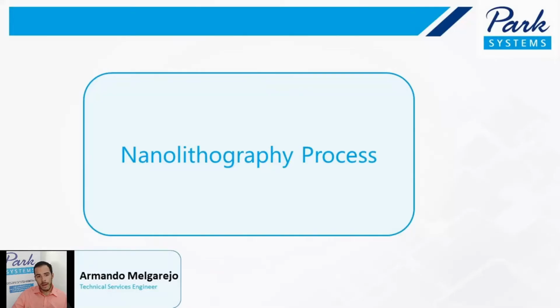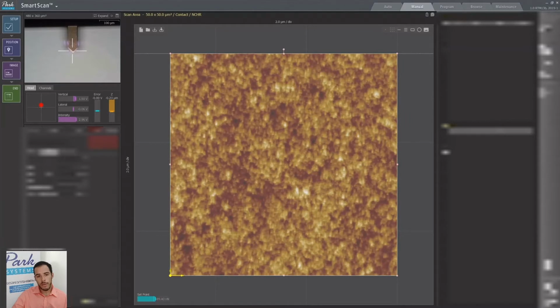If you look again above me, you will see that in between the scan and the spectroscopy window, there's a new option called the lithography window, Litho window. If you click there, we automatically activate the SmartLitho software. Once in there, you first select the mode you're going to use. As I mentioned before, here we have set point, Z-scanner, and bias mode. In this case, I'm selecting set point, and then I'm going to the options panel.